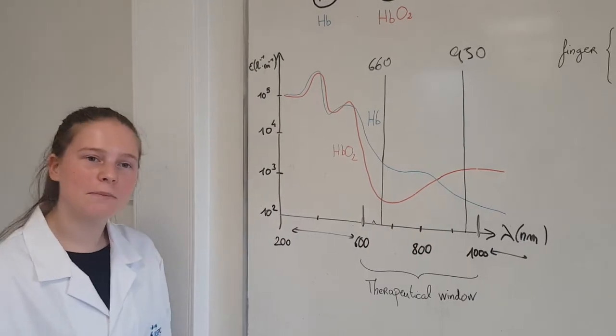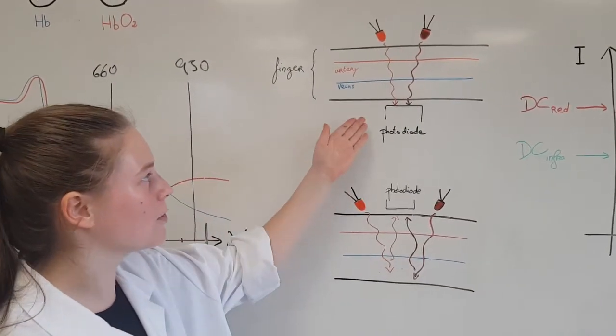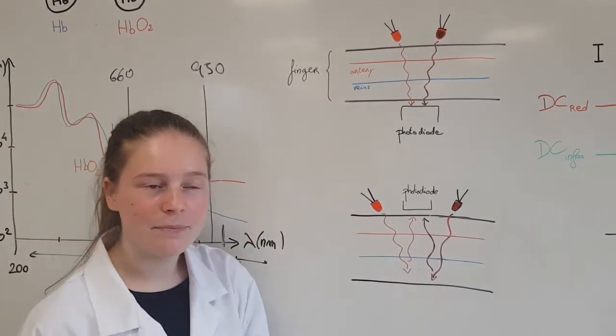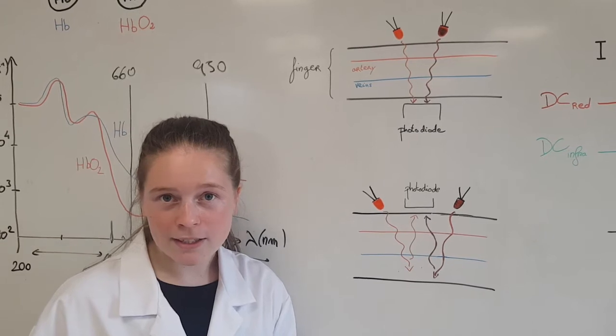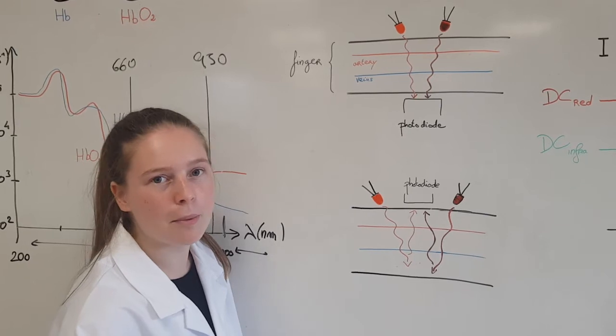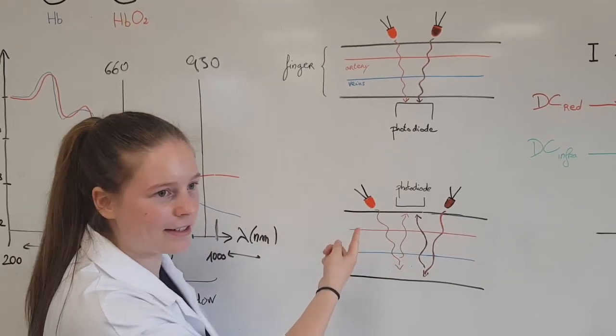Most oximeters use the light transmitted through the finger, meaning the photodiode collecting the light is put on the opposite side of the finger from the LED. But a small part of the light is also retro-diffused in the finger, so with our reflective oximeter we can collect light with the photodiode on the same side as the LED.